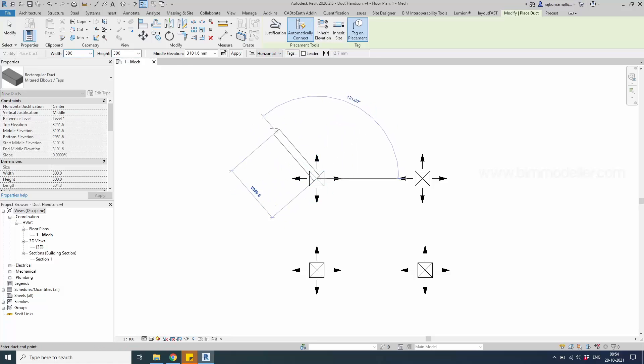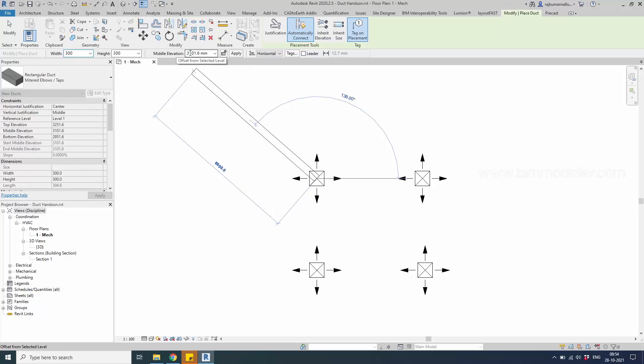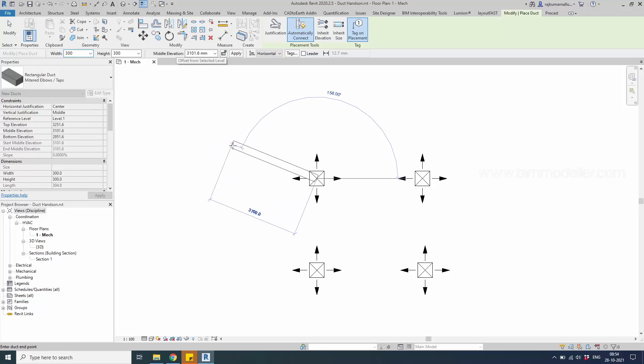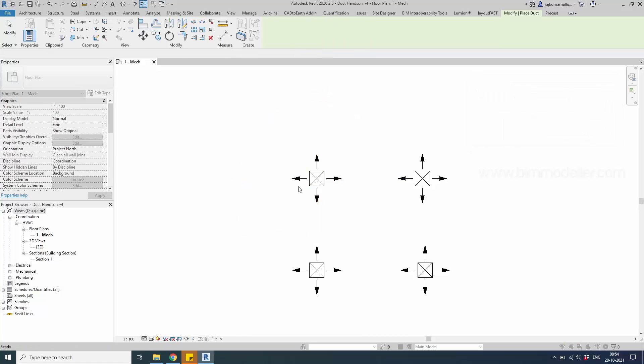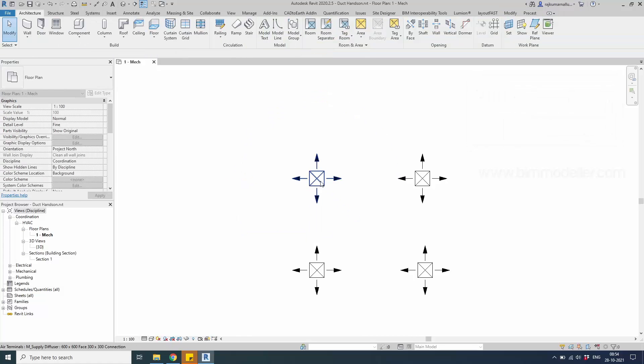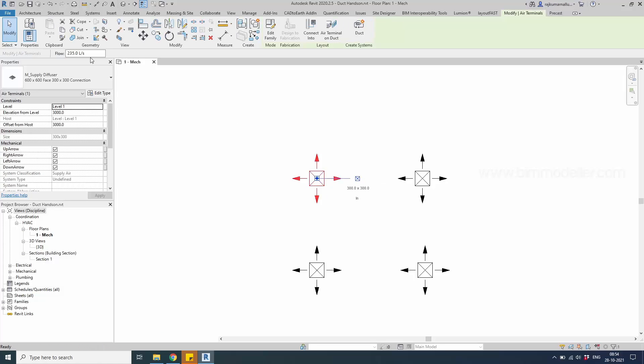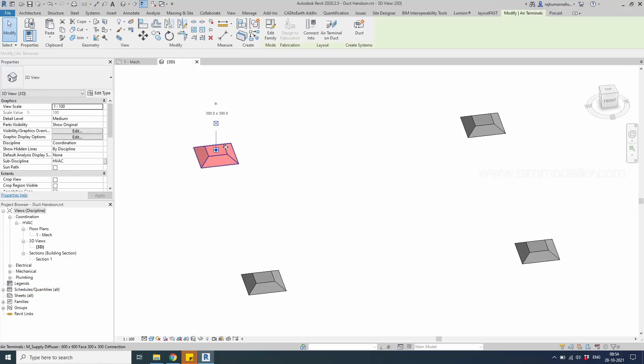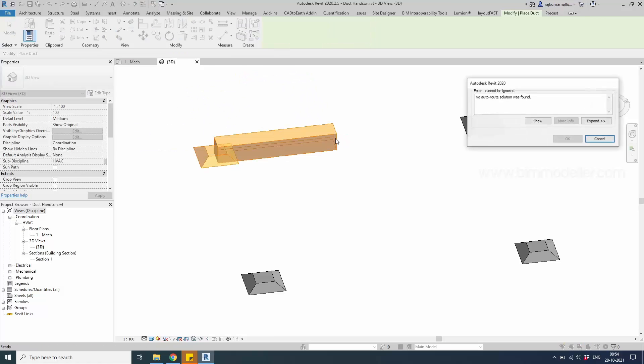If the elevation is something different — for example, 3101 — and you try to create the duct, it shows the same error again. To understand the reason, if you check in the 3D view and select this, Revit tries to place the duct in the same location, which causes the conflict.